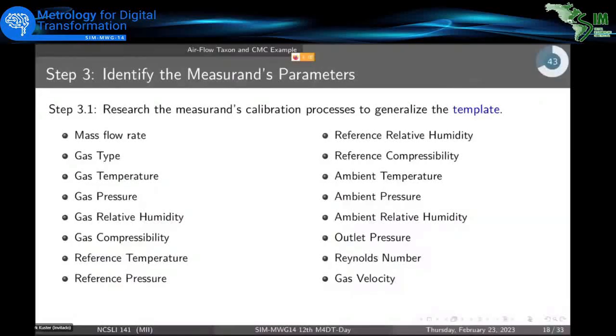And if we go out and research the process of mass flow rate, we find any number of different influences that might either alter the uncertainty or give options that the customer might want to choose between. Now, all these don't necessarily apply to any given lab situation. Depending on the uncertainty level, the traceability level, and the customer requirements, any given lab may drop any or all of these parameters from their particular CMC. But this is the abstract template that we want to develop to cover any situation.